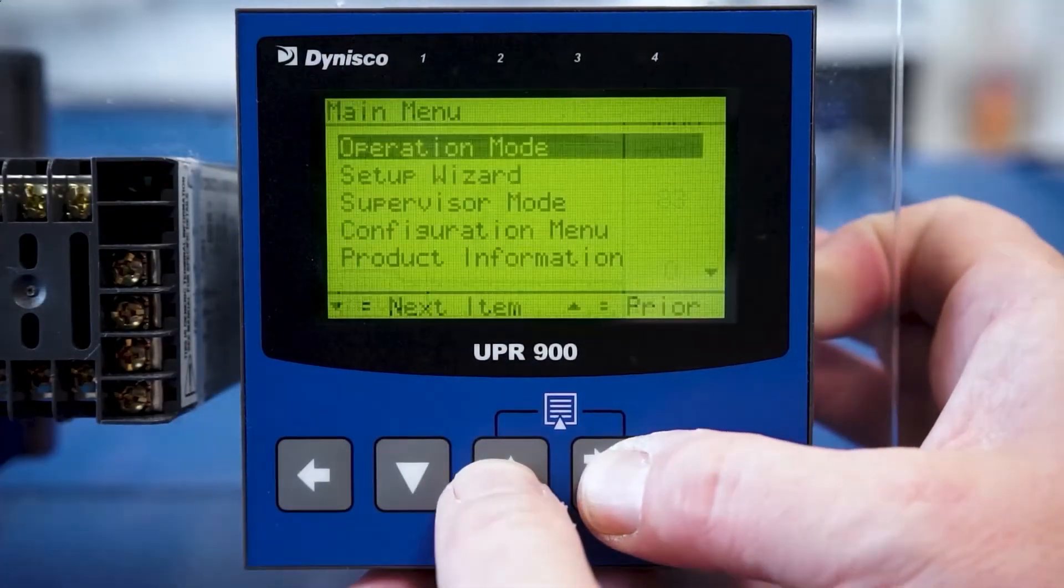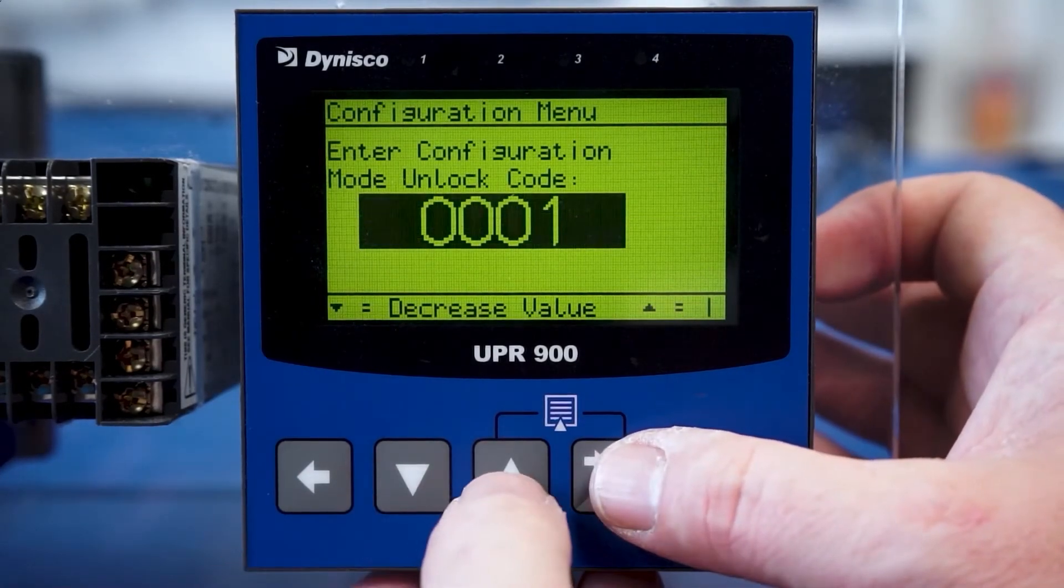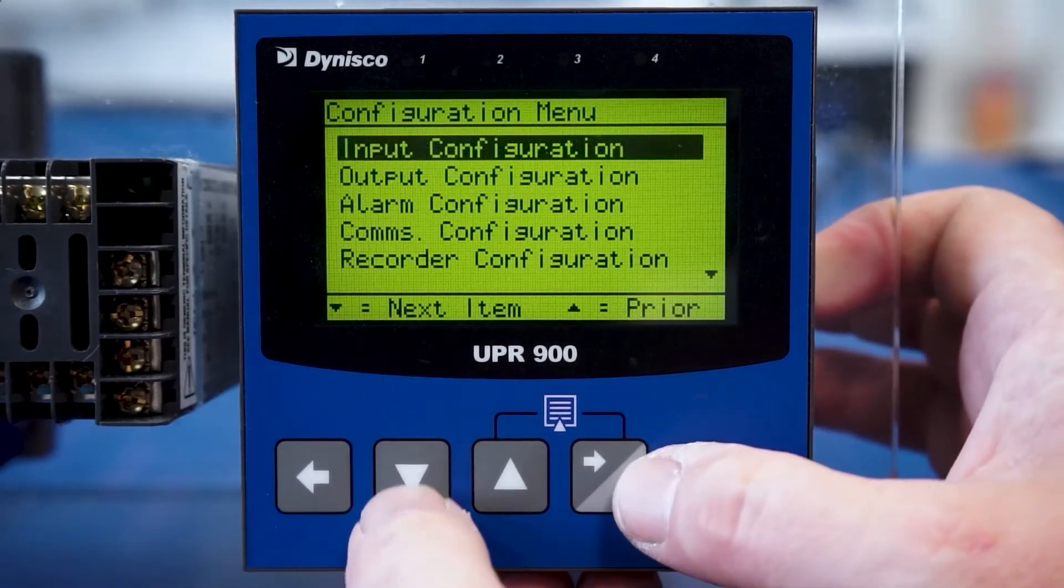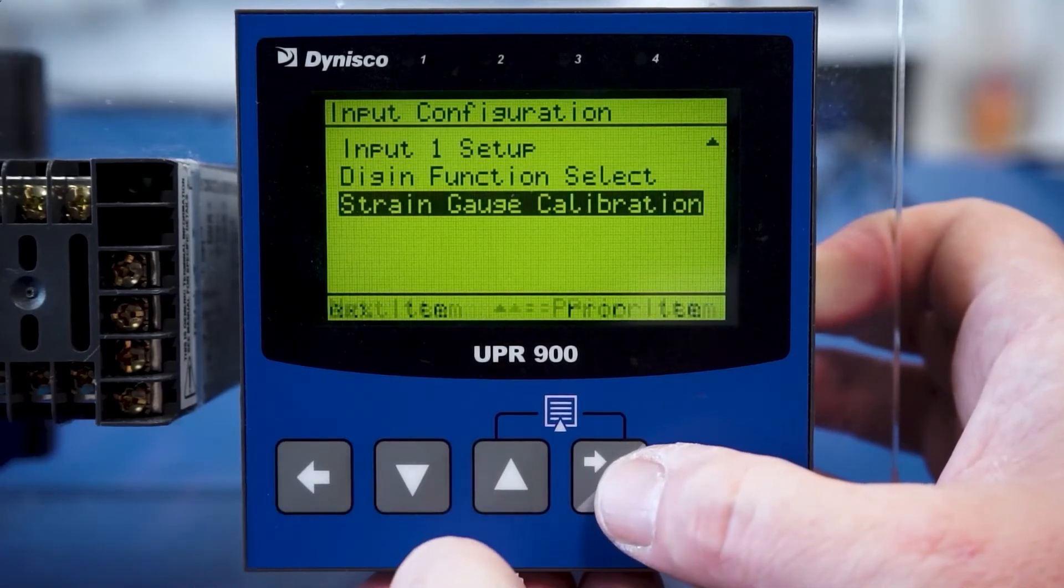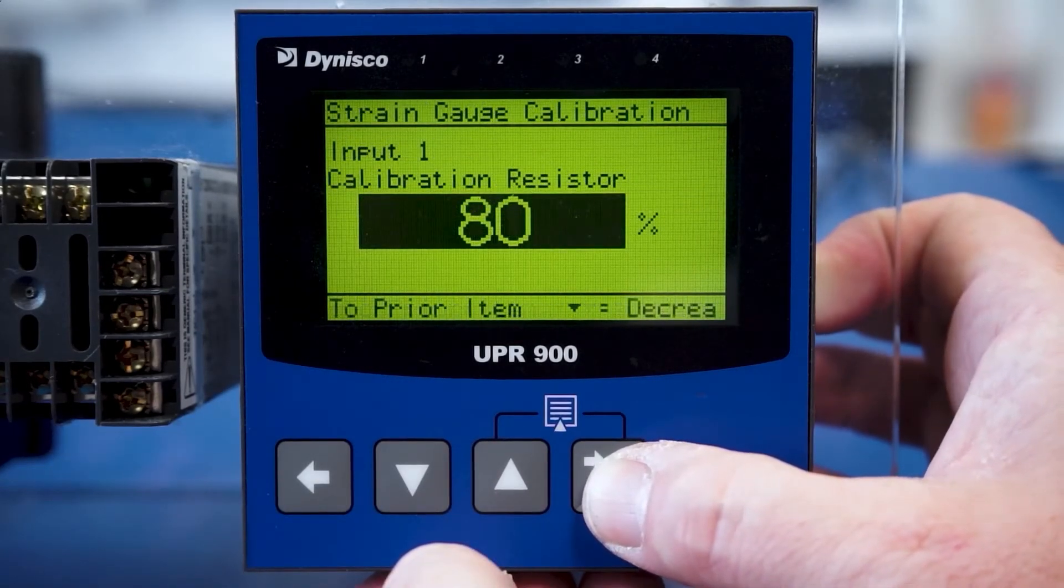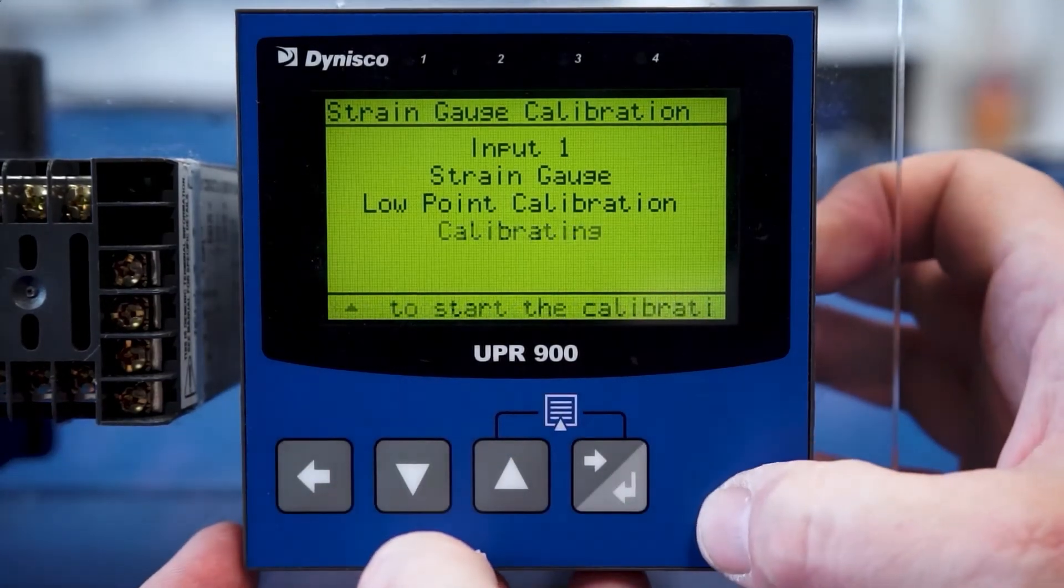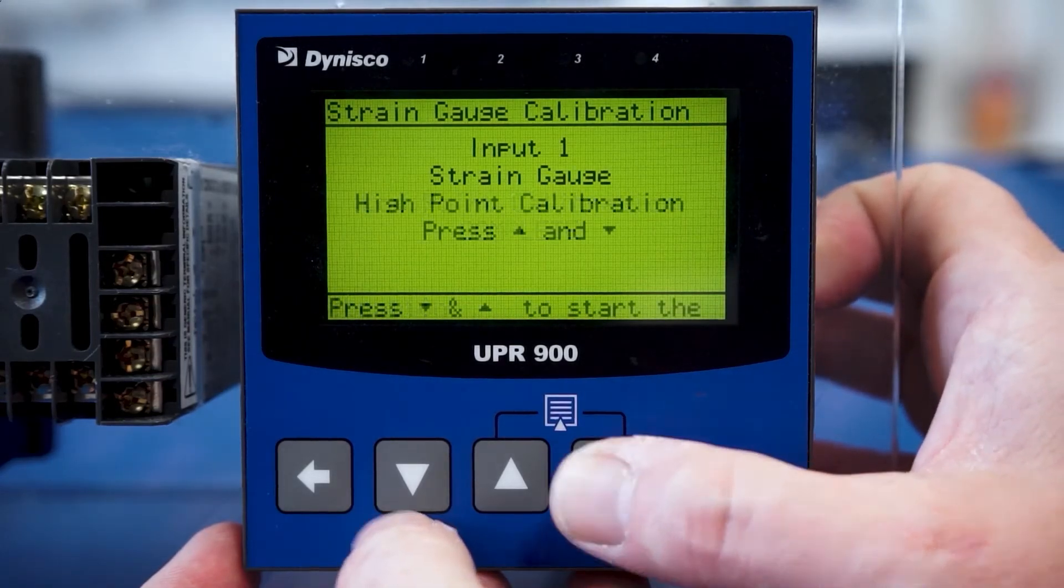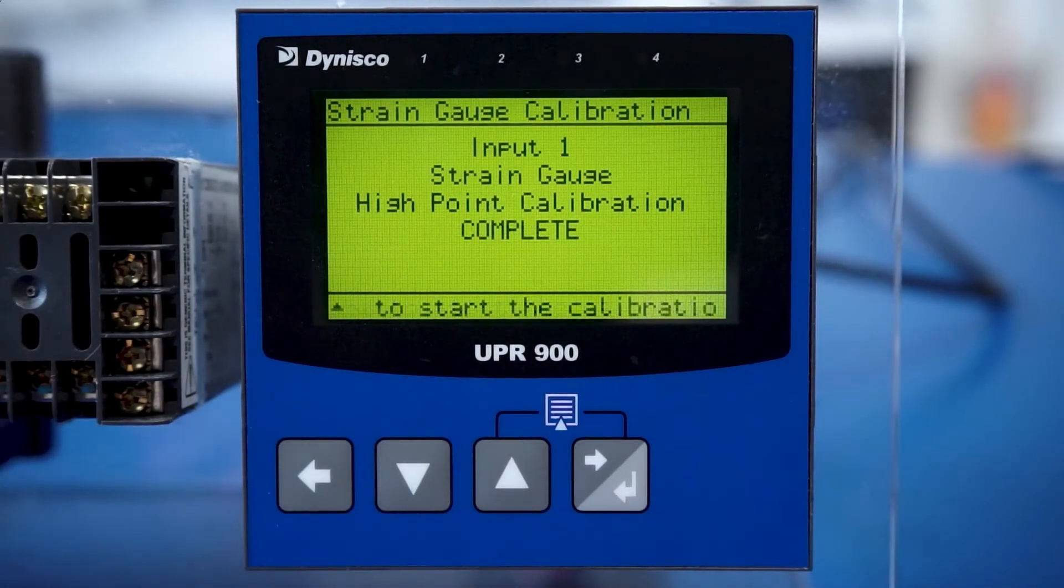The technician enters the submenu to access the configuration screen and enters the default unlock code of 10. Once in the configuration menu, the input configuration is selected to find strain gauge calibration. The instrument prompts the technician to test the high and low calibration points via the up and down arrow keys as demonstrated. Once the high and low points have been tested, the indication device will show calibration complete.